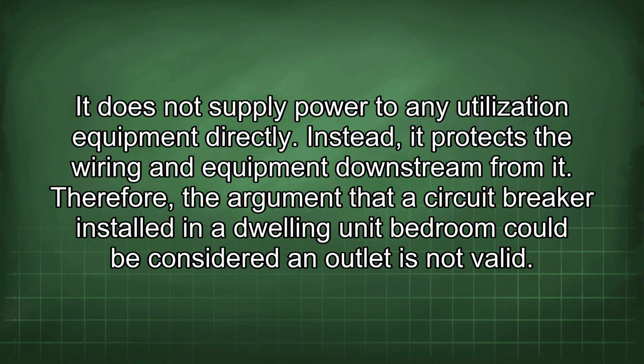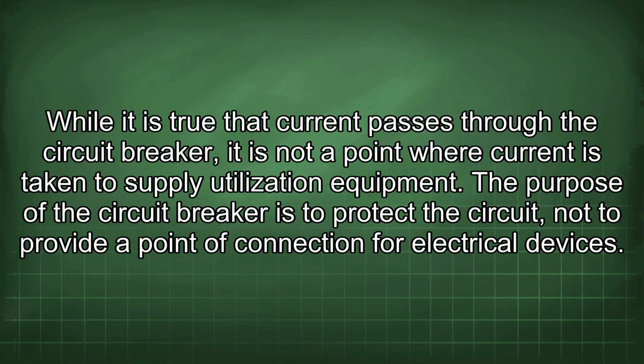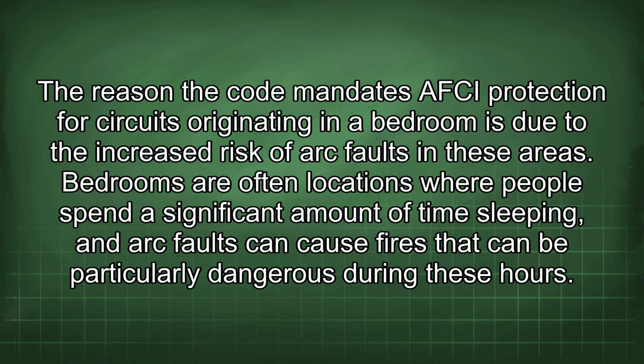Therefore, the argument that a circuit breaker installed in a dwelling unit bedroom could be considered an outlet is not valid. While it is true that current passes through the circuit breaker, it is not a point where current is taken to supply utilization equipment. The purpose of the circuit breaker is to protect the circuit, not to provide a point of connection for electrical devices. The reason the code mandates AFCI protection for circuits originating in a bedroom is due to the increased risk of arc faults in these areas.